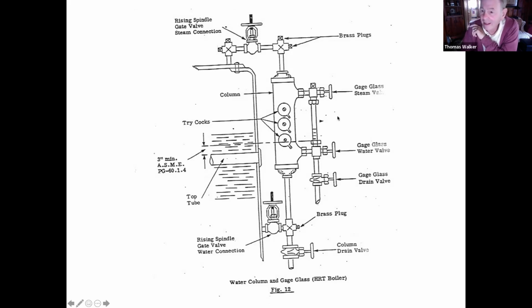Attached to the water column, that's usually where they attach the primary low water cutout. So if you blow down the water column or the gauge glass, the boiler will trip, unless the boiler is equipped, as most of them are, with a low water disable switch. That cuts out the low water cutoff, gives you an audible alarm, but it doesn't trip the boiler. Does everybody kind of get that?